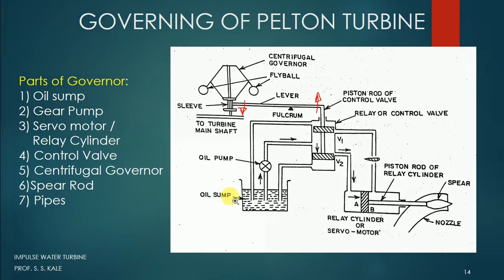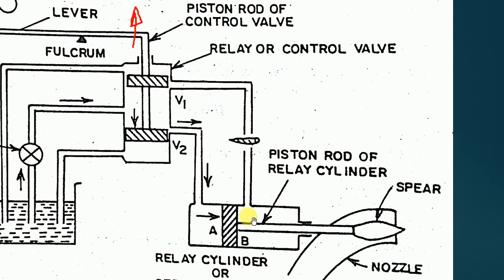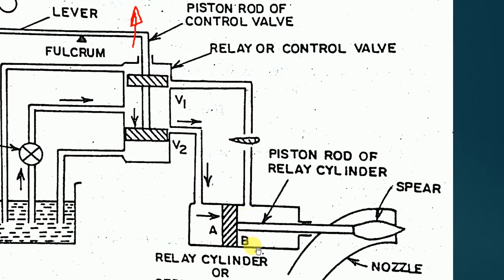Now the oil coming from the pump is connected to V1 rather than V2. From V1, the oil enters the rod-side part of the piston — zone B. When this oil arrives, it increases the force on the piston, and as the force increases, the piston moves towards the left. As the piston moves left, the spear also moves left, coming out from the nozzle.